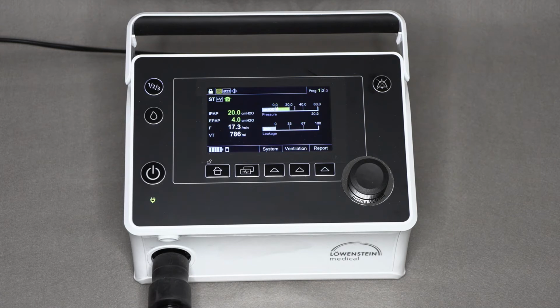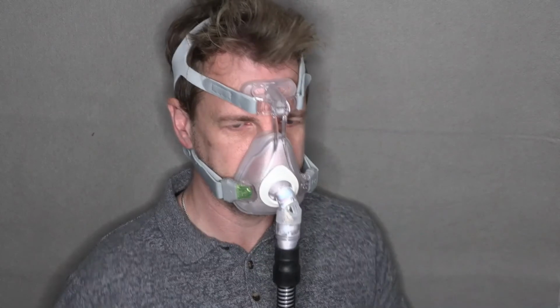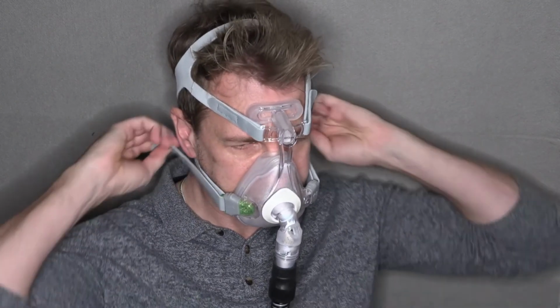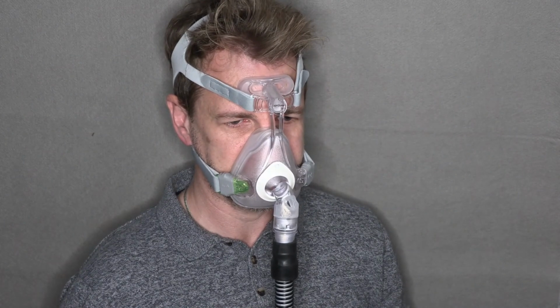Once your mask is secure, you can continue to use the ventilator through the night or as recommended by your prescriber. If the mask is not secure or tight enough, there may be some leakage around the sides of the mask or into the eyes. It's important to have little or no leak from the mask. If mask leakage is excessive, there may be some alarm on the prismaVENT with an on-screen message warning of excessive leak. If this happens, it does not mean that something is wrong with the ventilator, but just means that you may need to tighten the mask more to prevent leak and also to prevent annoying alarms.